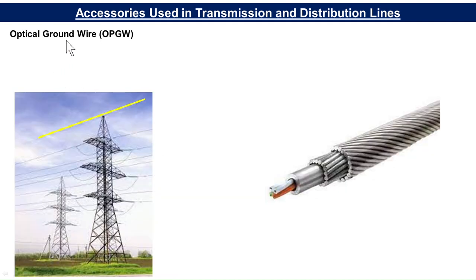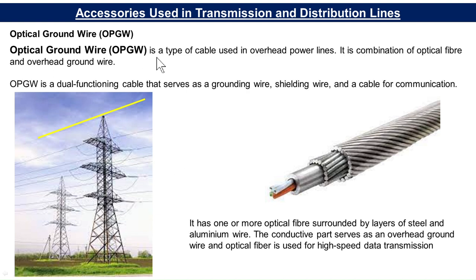Then there is the optical ground wire (OPGW). This is the latest technology in transmission, where the ground wire is replaced by an optical ground wire. It has two parts: an aluminum sheath on the outside and optical fibers inside. OPGW is a dual-function cable used in overhead power lines — it serves as a ground wire and shielding wire, and also as a cable for high-speed data communication. The conductive part acts as the overhead ground wire and the optical fiber is used for high-speed data transmission.